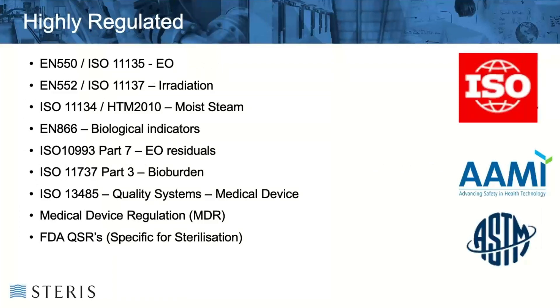When one reflects on the ISO definition and the words 'planned and systematic actions,' it becomes apparent as to why we are highly regulated. Sterilization has a vast array of international and regional standards agreed through consensus by subject matter experts and industry stakeholders. These standards define normative requirements necessary for compliance and also provide informative guidance to assist users demonstrate compliance with industry best practice. For example, ISO 11135 is applicable to EO sterilization, ISO 11137 applies to radiation processes, and there are supporting standards for biological indicators, ethylene oxide residuals, and microbiology-based testing.